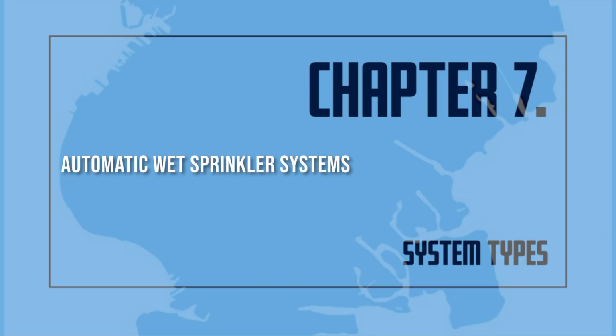Automatic sprinklers are very effective for life safety. They signal the existence of a fire. At the same time, they discharge water to the burning area. When sprinklers are installed, there are rarely problems getting water to the seat of the fire. They also reduce interference with visibility for firefighting due to smoke. The downward force of the water sprayed from sprinklers lowers the smoke level in the room. The sprinklers also serve to cool the smoke. This makes it possible for persons to remain in the area much longer than they could if the room were without sprinklers.